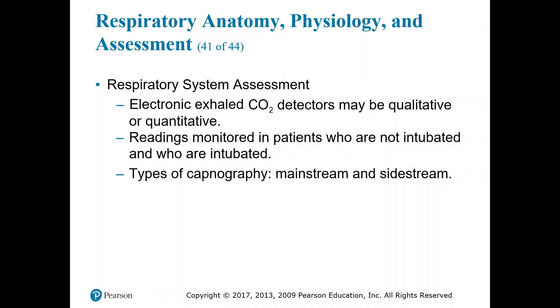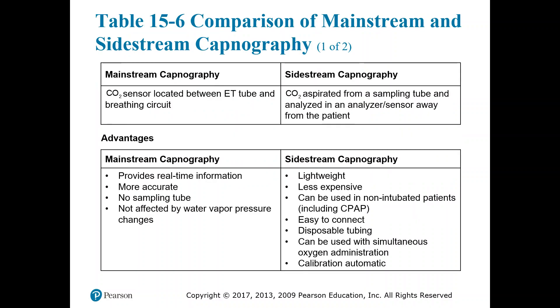With sidestream, you have a little bit of a delay. The advantages of mainstream capnography are that the CO2 sensor is located directly between the ET tube and the breathing circuit — as close to the patient as it could possibly get — and it measures the total amount of CO2 coming across its sensor. It provides real-time information and is more accurate because it's sampling the entire gas passing across its sensors. There's no sampling line and it is not affected by water vapor or pressure changes.